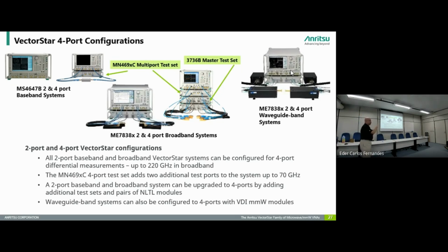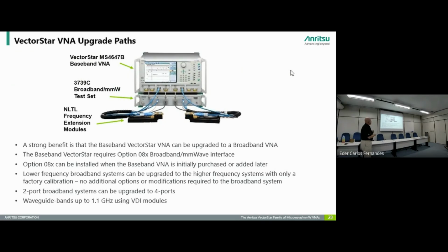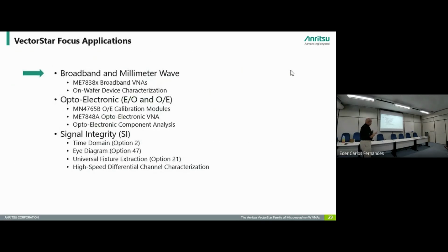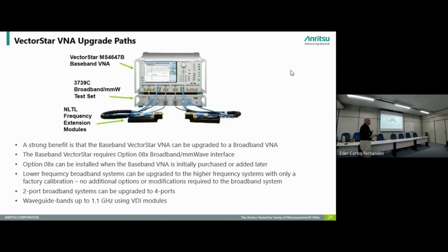So you've got all this upgradability and modularity built into the system. But it all begins again with the baseband VNA and the fact that the VNA needs to be configured with the broadband interface. That's basically these 3 connectors across the top. That's a hardware option, but that's what provides the RF and the LO to the millimeter heads. So that's a hardware option that needs to be in place. But if it's in place, we can upgrade into the millimeter ranges. And we can also upgrade up to 4 ports by adding additional test sets or the waveguide modules for VDI. So one of our strongest benefits is the fact that it's modular. Everything's modular.